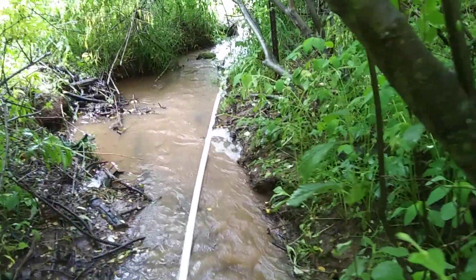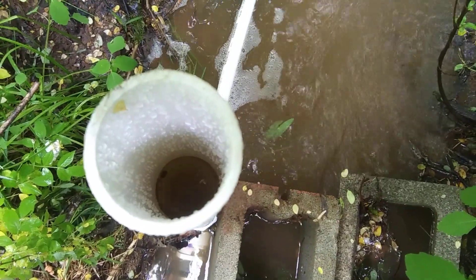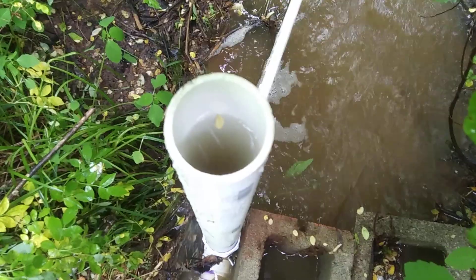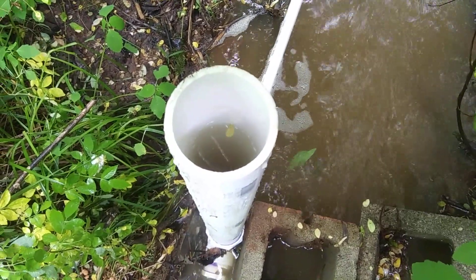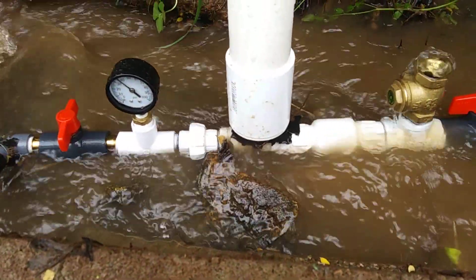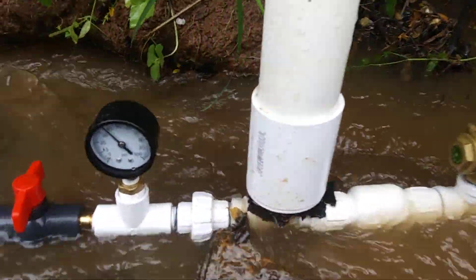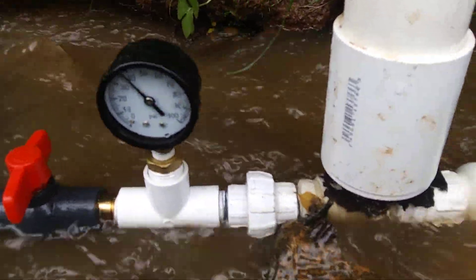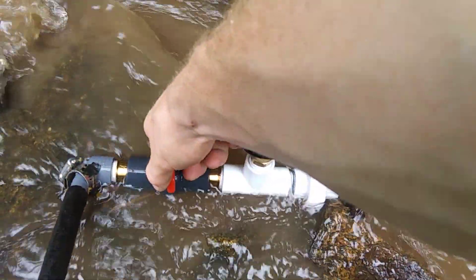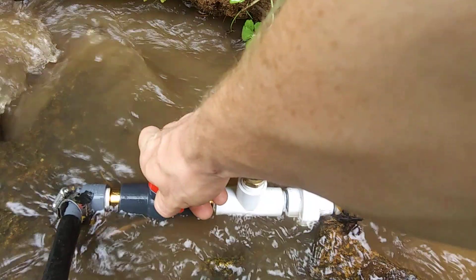This would be the drive pipe. It is a little bit higher — I just waited a minute and that's much higher now. You can see I've got about 35 pounds on the pressure gauge right there. I'm going to open this valve right here, and that will decrease by quite a bit.